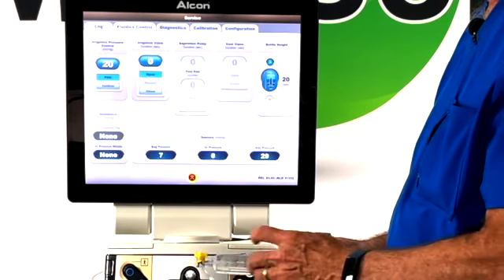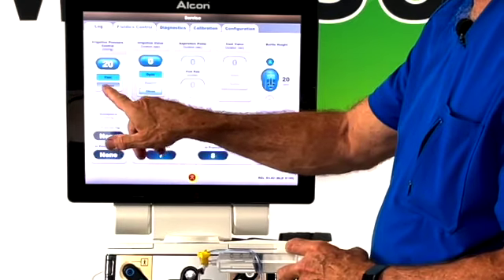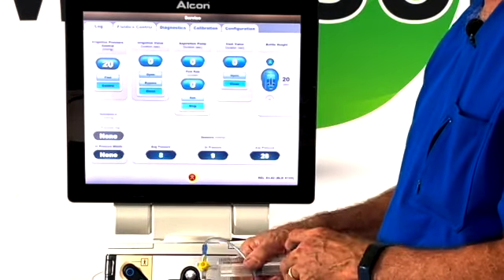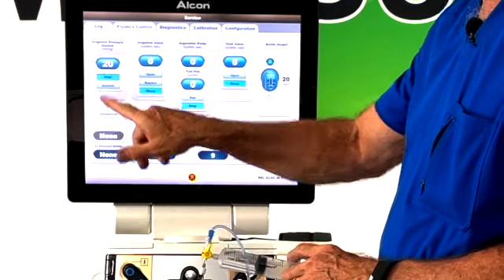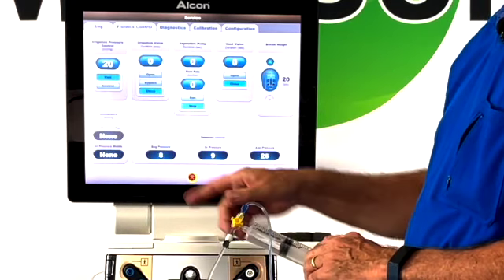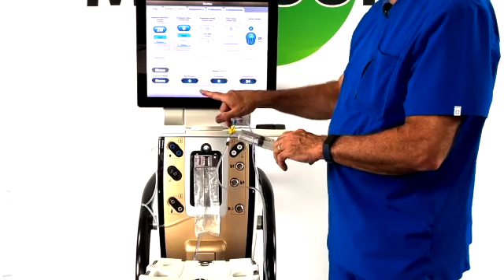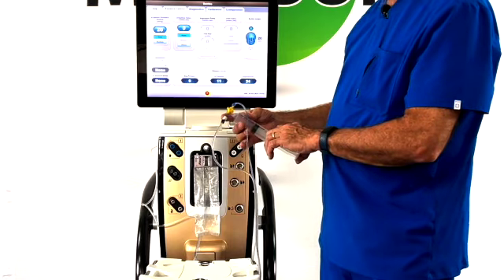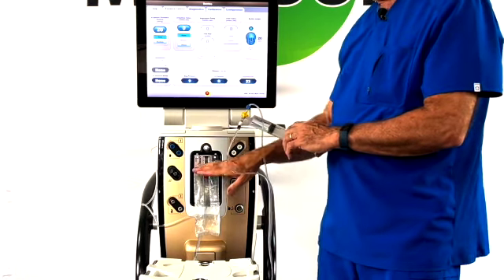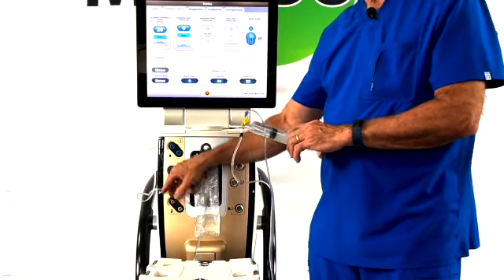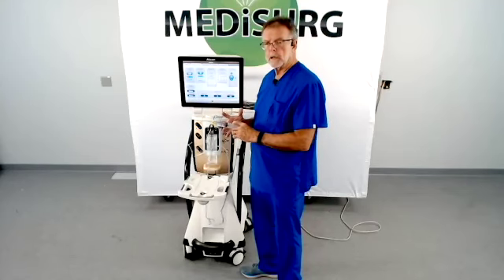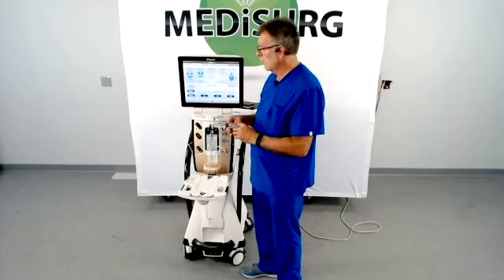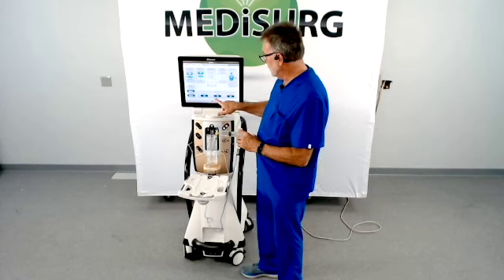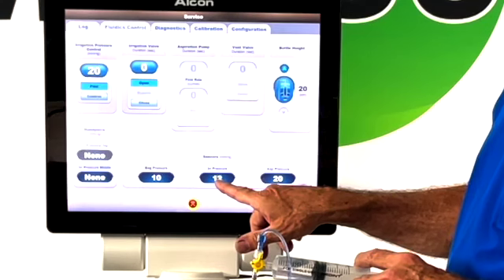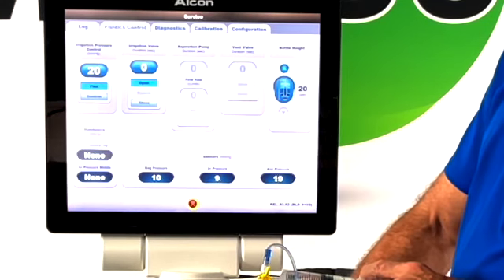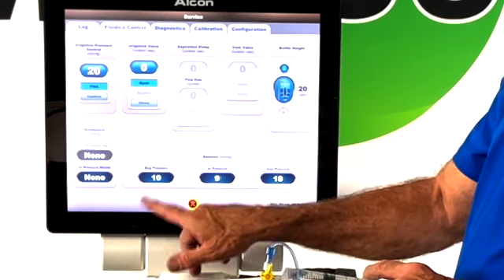Okay, and I'm going to toggle this for a second, come back to find, and then open. So now I've got an opening between my syringe, through the cassette, through this line to the bag. So now I'm going to pressurize the bag using the syringe and check the numbers. So here's the irrigation sensor that we checked earlier. So I'm going to read it here and also read it there.